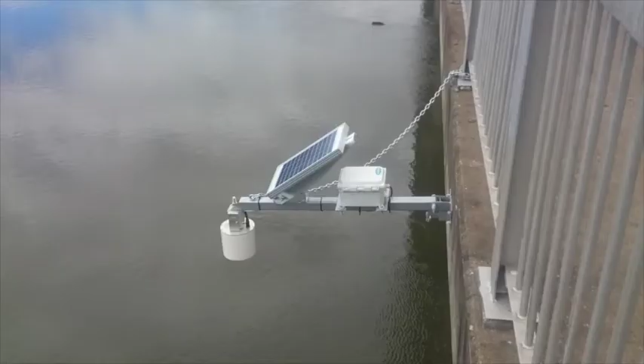Ultrasonic and radar type sensors are fixed on a platform over the water body. It may happen that the fixture is disturbed and the orientation of the sensor cone goes wrong. The sensor should look straight at the water surface. If it is looking in a different direction, then there will be wrong data. So we have to fix it.